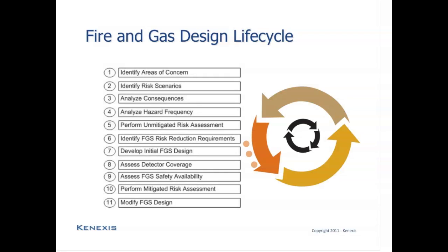You're going to want to use your heuristics from experienced fire and gas systems engineers to provide an initial design, an initial layout based on the type of equipment, the type of facility and how the various pieces of process equipment and support equipment are laid out. All of the initial design is performed using heuristics or rules of thumb. But the difference between the previous way of designing fire and gas systems and what is espoused in the ISA 84.00.07 technical report is that we don't stop using rules of thumb.